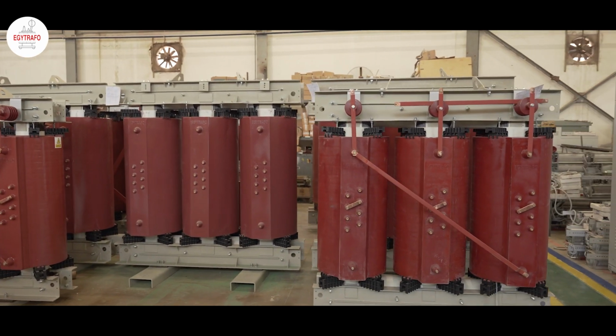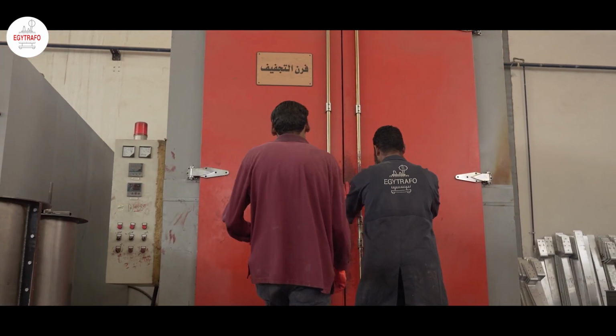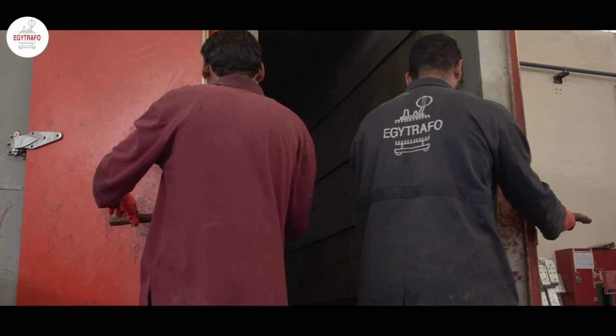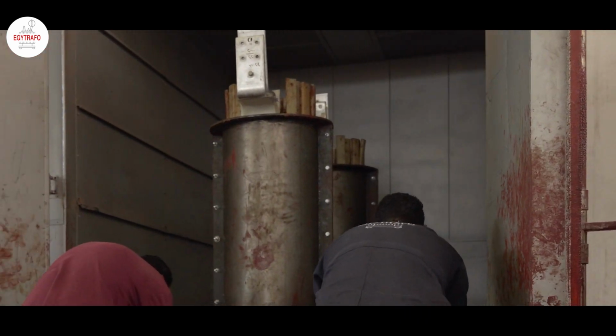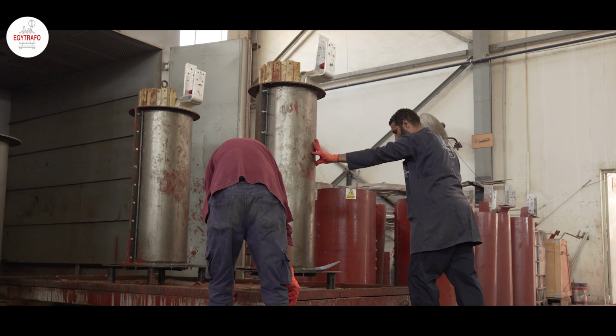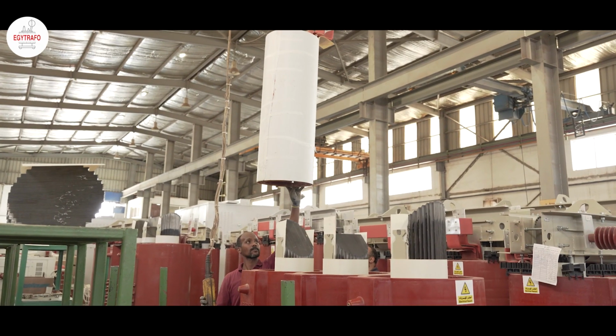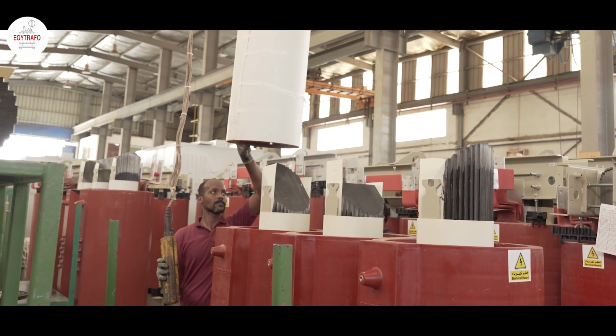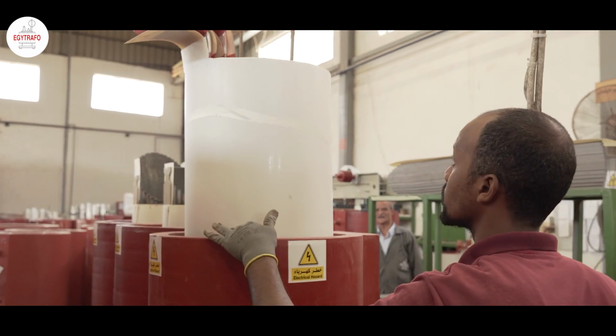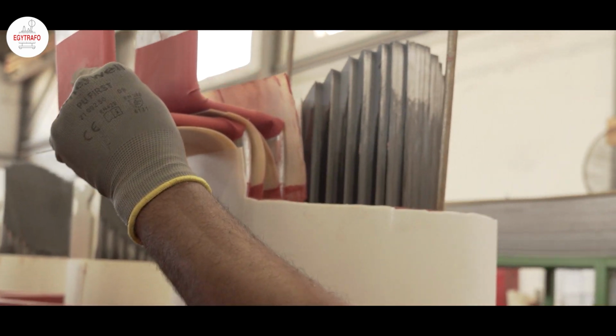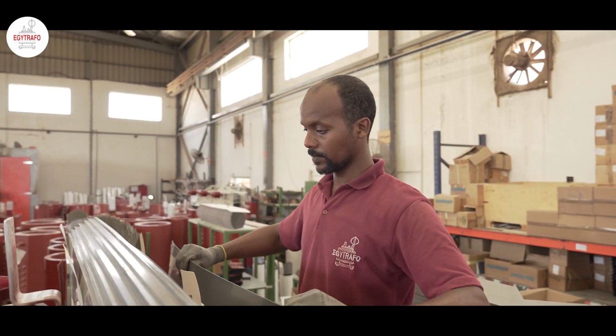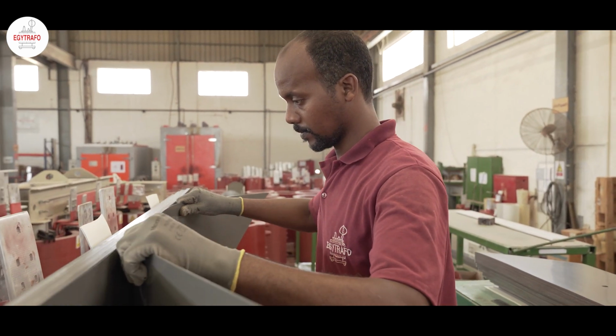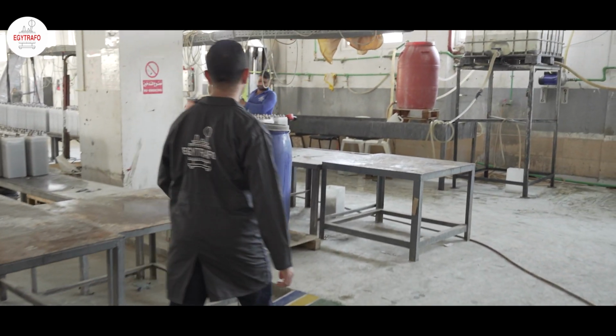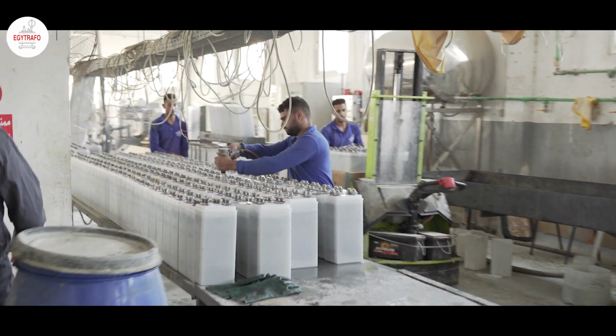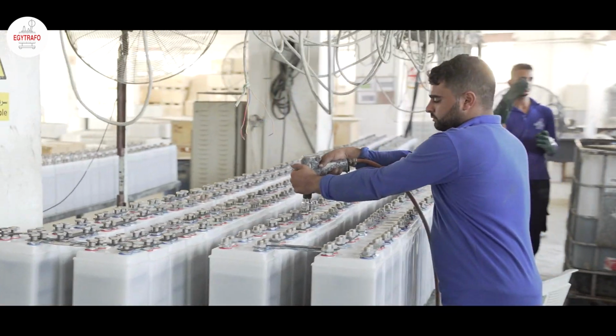Egytrafo can manufacture dry cast resin transformers up to 4 megavolt ampere, 33 kilovolts, according to IEC 60076-12. The casting oven availability facilitates casting of different winding types, either aluminum windings for both low voltage and high voltage, or copper windings. All Egytrafo's manufactured transformers undergo all routine tests during each manufacturing phase and before being delivered to clients. With cooperation with Saft, the world first-class battery manufacturer, we manufacture nickel-cadmium batteries up to 800 ampere-hours.